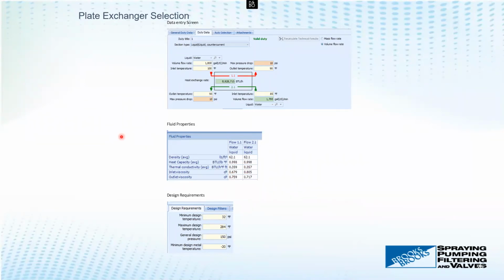Off the top of my head, if it's hydrochloric acid, we may not have the right plate material at certain percentages, because graphite is the one that cannot be pressed into a plate heat exchanger. But we can look into other materials we have, like hastelloys, titanium, and so on. The most important thing is it should be completely resistant to corrosion. That's the material we use, otherwise we just won't be able to offer a solution.